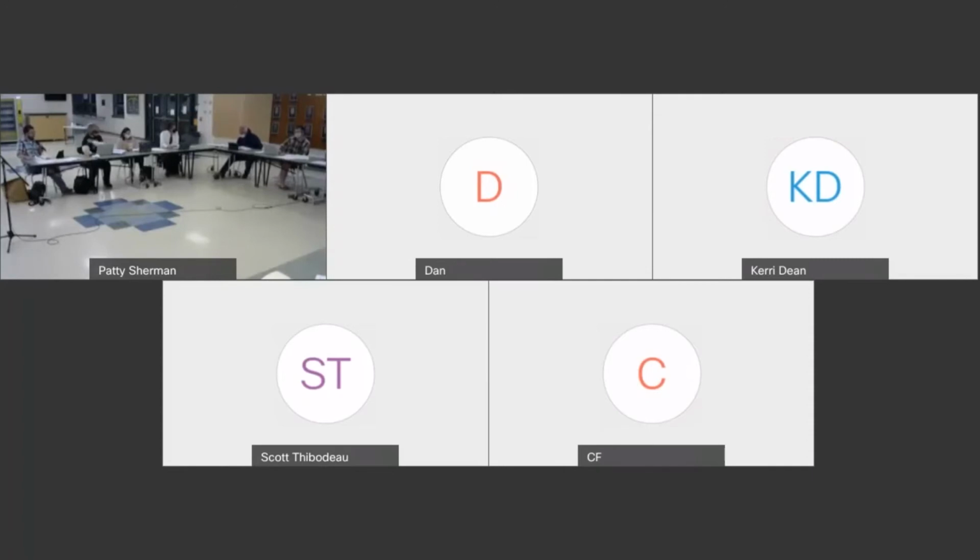And then HVAC, we really think the unit ventilators should go. They're noisy, they're localized. Create, whether it's a rooftop option, something above the ceiling grid line but below the roof line, or something ground mounted outside the building on the perimeter somewhere that feeds into a ductwork network, a centralized quiet HVAC option with proper air handling, exchange, filtration, heating, dehumidification. That does not really exist.